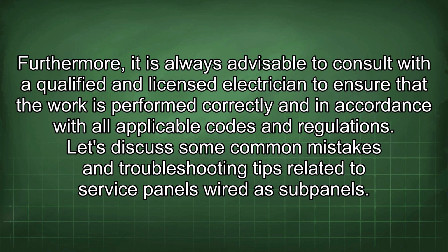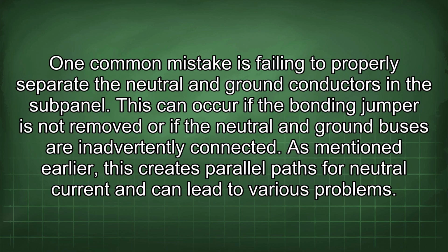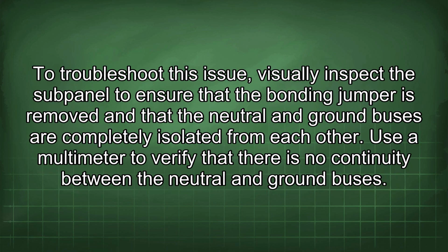Let's discuss some common mistakes and troubleshooting tips related to service panels wired as subpanels. One common mistake is failing to properly separate the neutral and ground conductors in the subpanel. This can occur if the bonding jumper is not removed or if the neutral and ground buses are inadvertently connected. As mentioned earlier, this creates parallel paths for neutral current and can lead to various problems. To troubleshoot this issue, visually inspect the subpanel to ensure that the bonding jumper is removed and that the neutral and ground buses are completely isolated from each other. Use a multimeter to verify that there is no continuity between the neutral and ground buses.